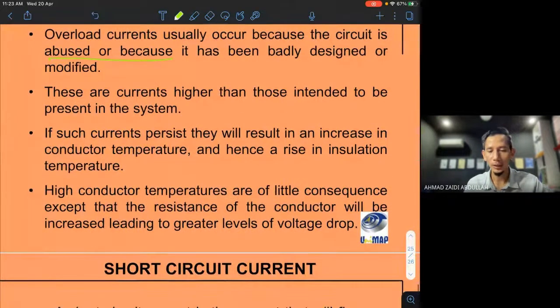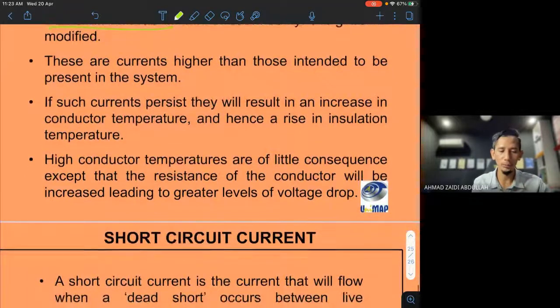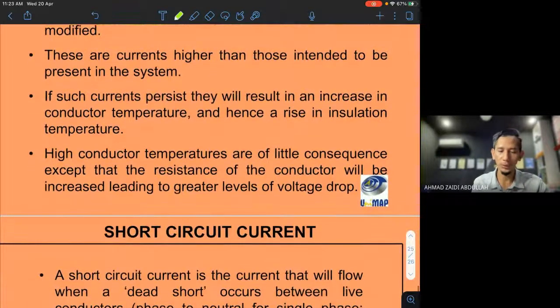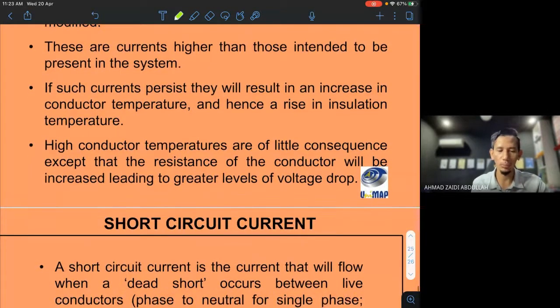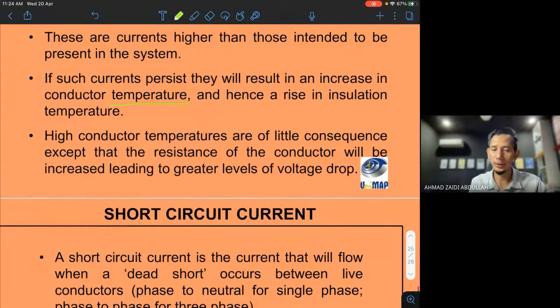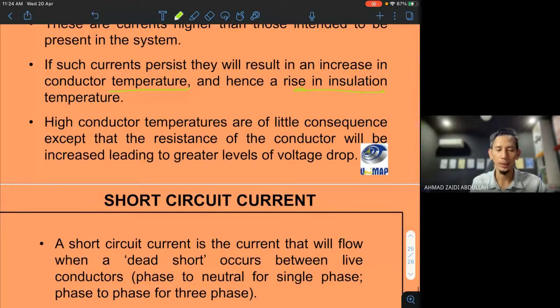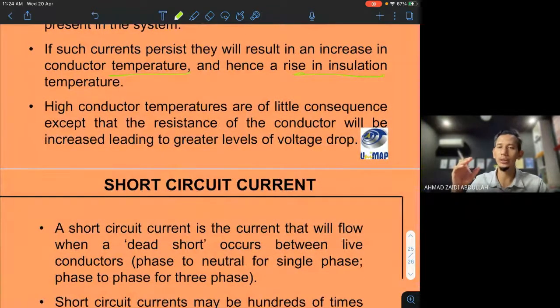And then this current is higher than what is intended to be present in the system. If such current persists, it will result in increased conductor temperature because of the overcurrent, kan. Overload tu, bila nampak more current required, it will produce very high current, high temperature. High temperature will raise the insulation temperature. And then when the conductor is at high temperature, confirm the insulation of the cable will melt.